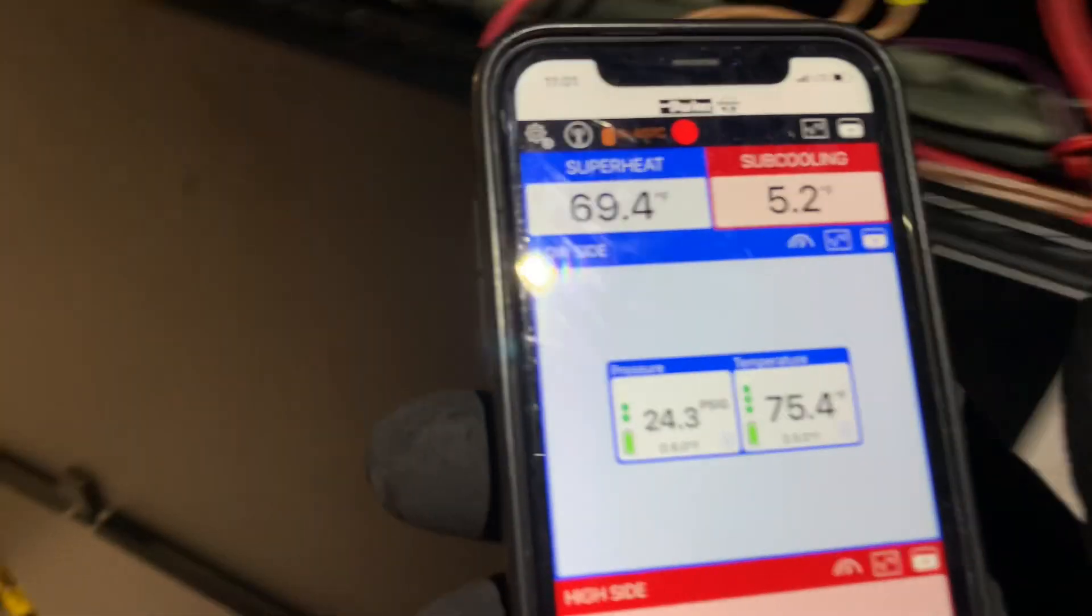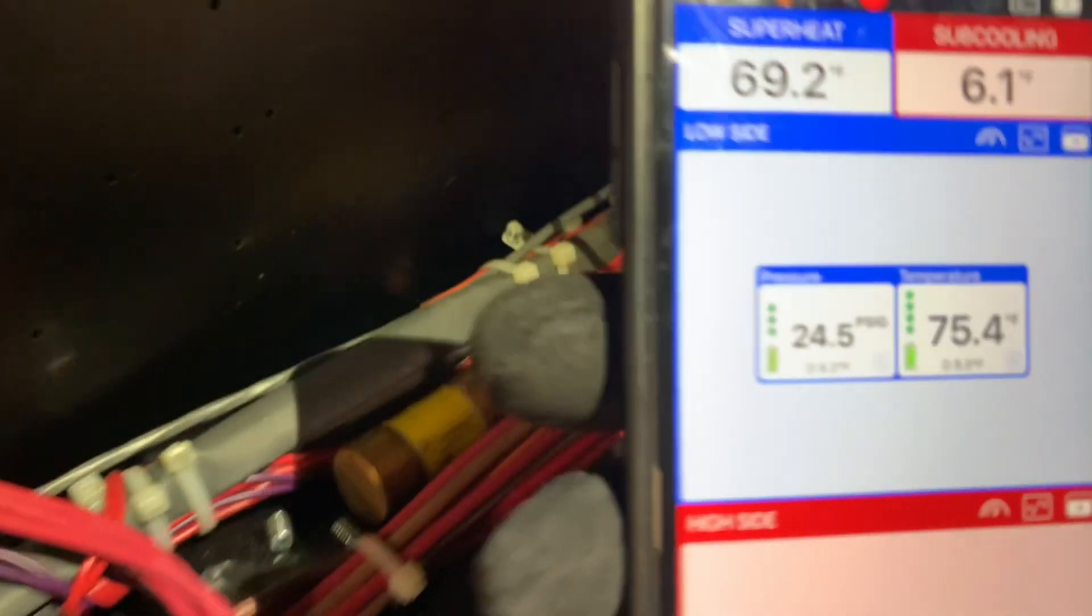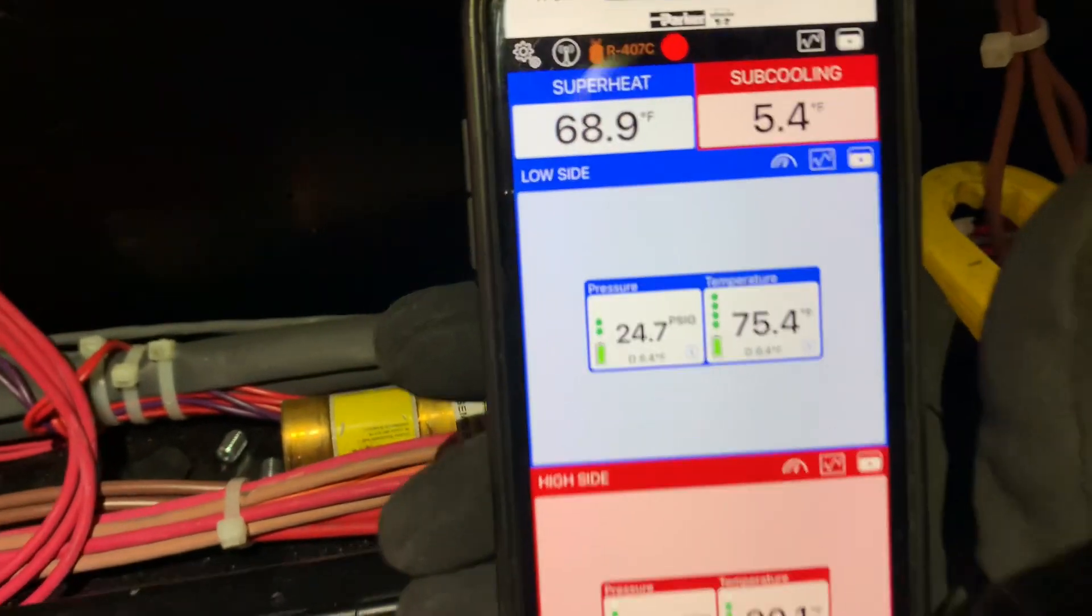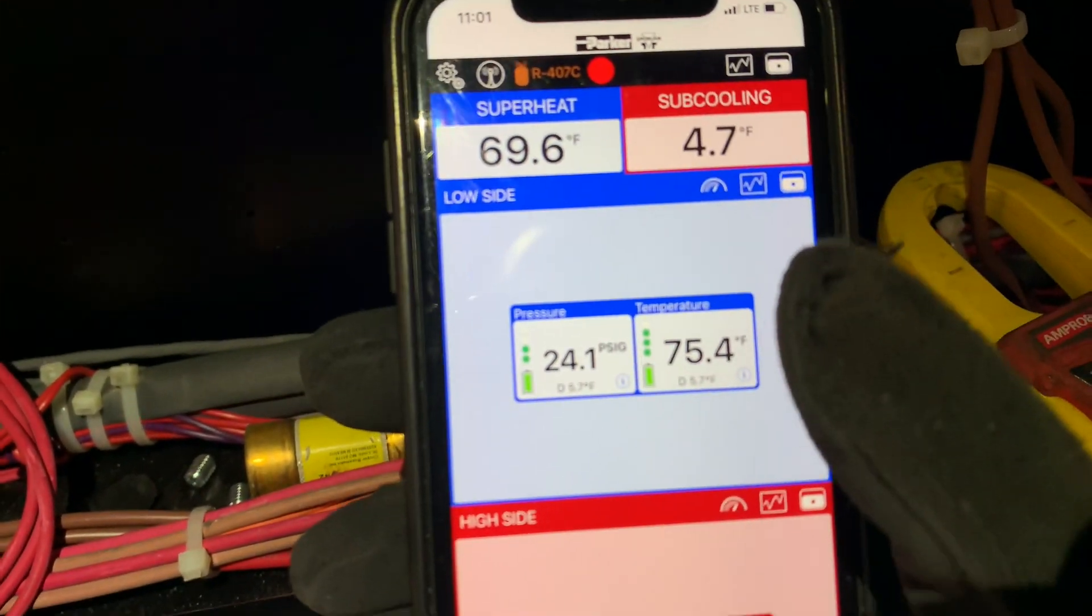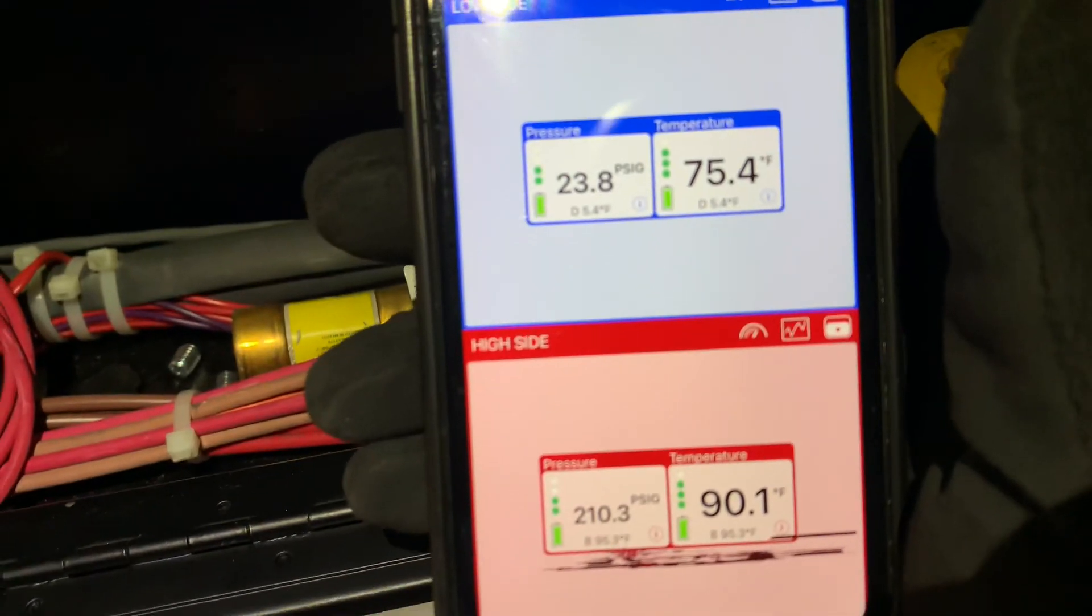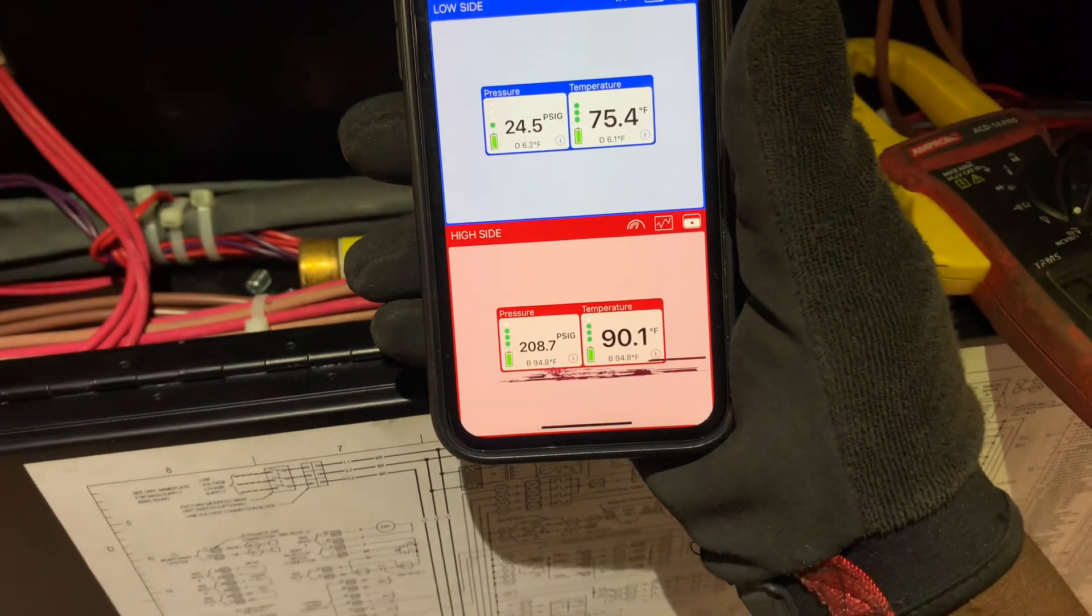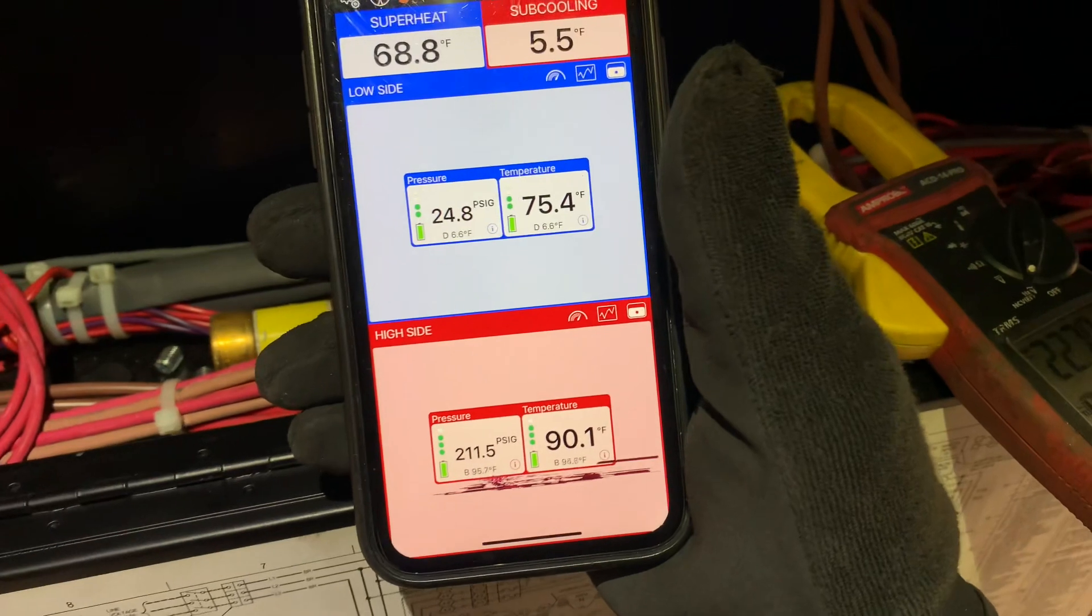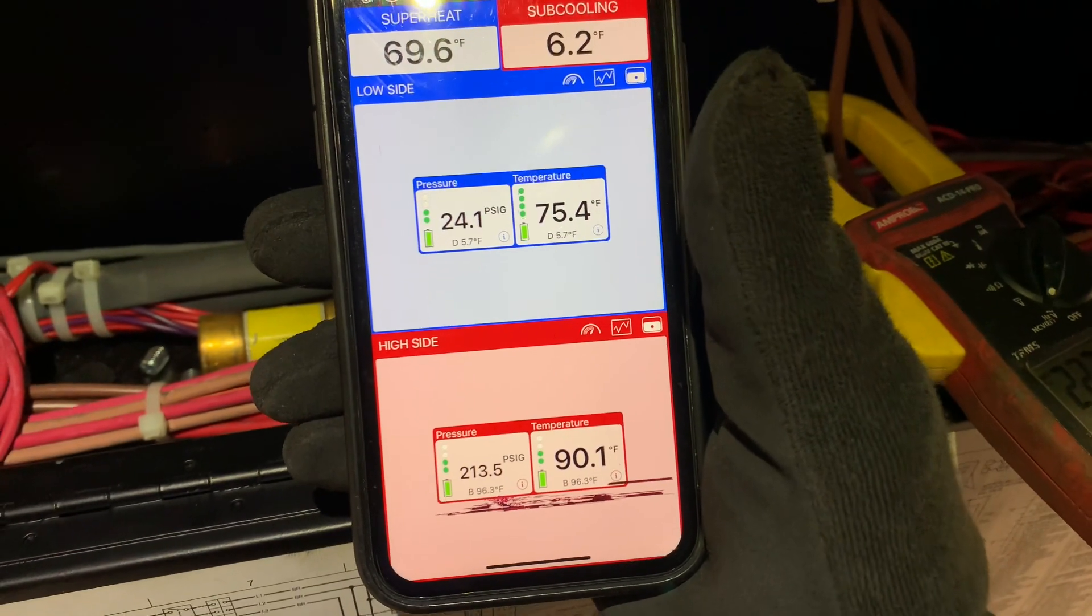So in this case, you can see that it's just low on refrigerant. So in this case, we have a leak, because we have high superheat, and we have loss of cooling. We have low evaporator pressure, or reasonably normal, or somewhat close to normal.